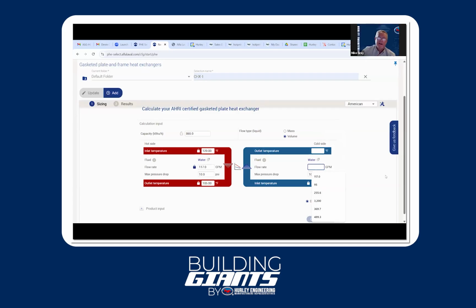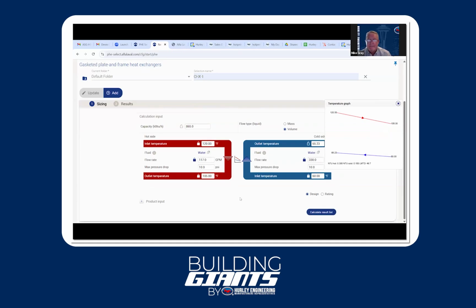Yeah, in this application we're doing some passive cooling. We had a flow rate requirement that we needed, so we'll leave that one in there and not do the outlet temperature - we'll let the system calculate that for us. You can see on this one, like we discussed before, it's closer to parallel, so we've got a good gap here and good heat transfer. It's not a close transfer, we're just trying to get as much of the heat as we can from one side to the other. And this one needed to be 316 stainless, so I can change that here.